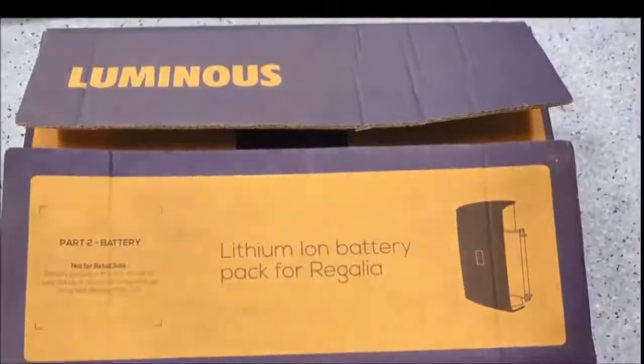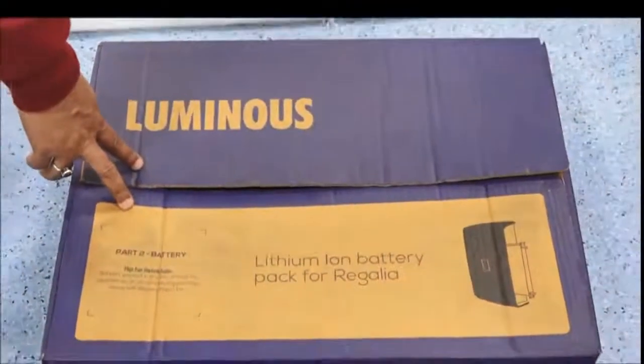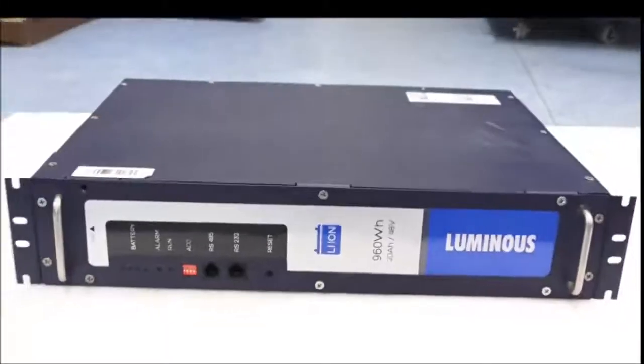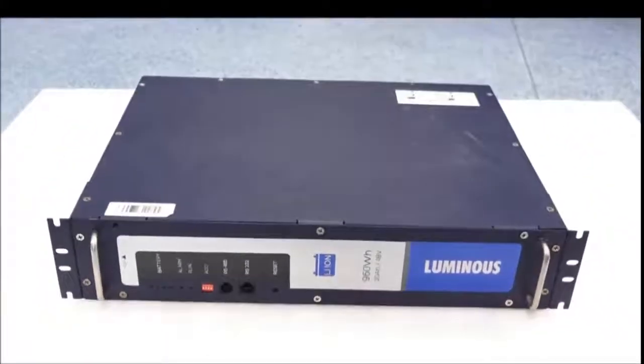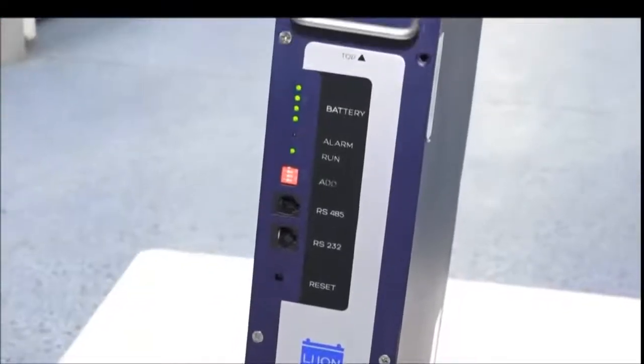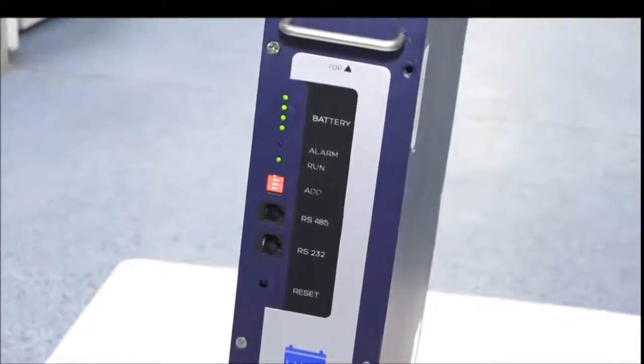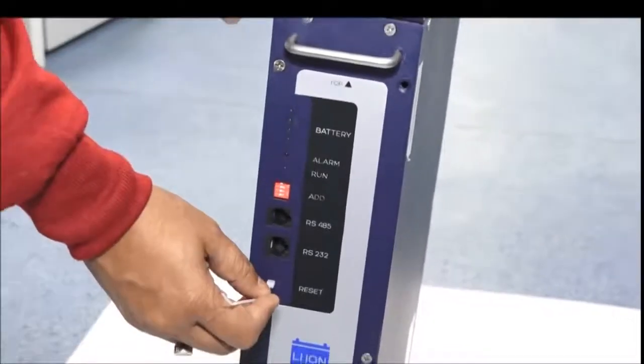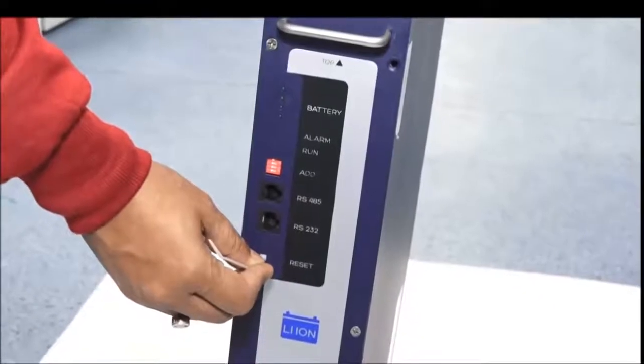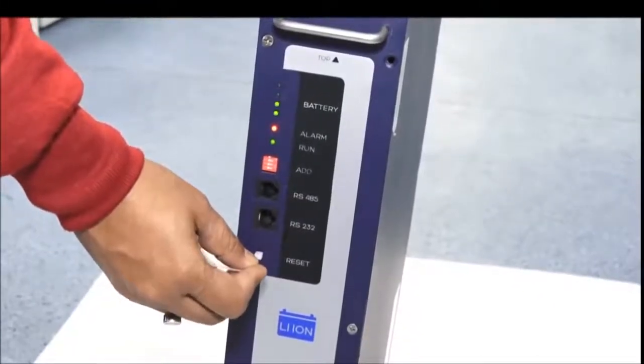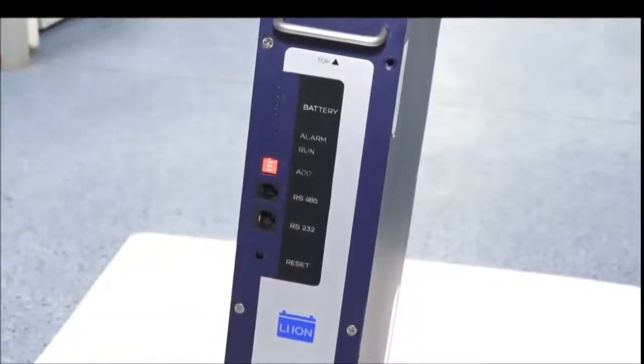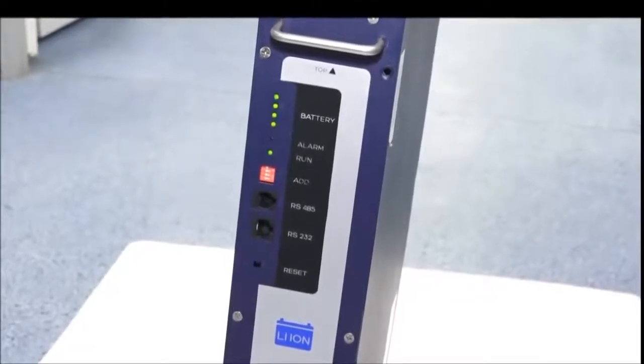Next, we will open Regalia's battery from the second box. Lift the battery and keep it on the foam packaging sheet. The battery has three types of LEDs labeled battery, alarm, and run. First, check the battery by pressing the reset button for 5 seconds using a screwdriver or the end of a cable tie. This also turns on the battery.